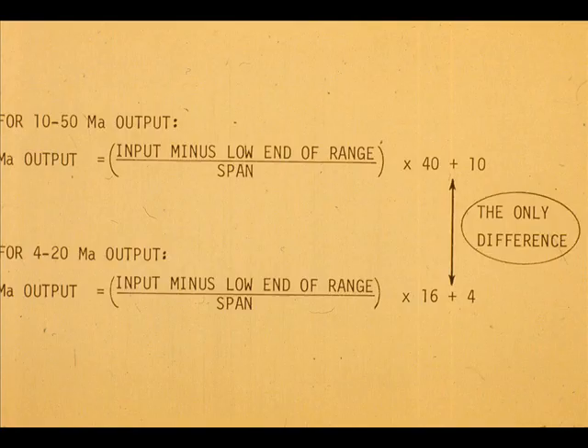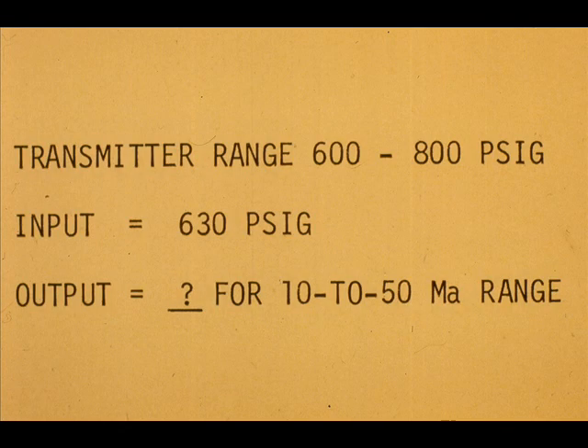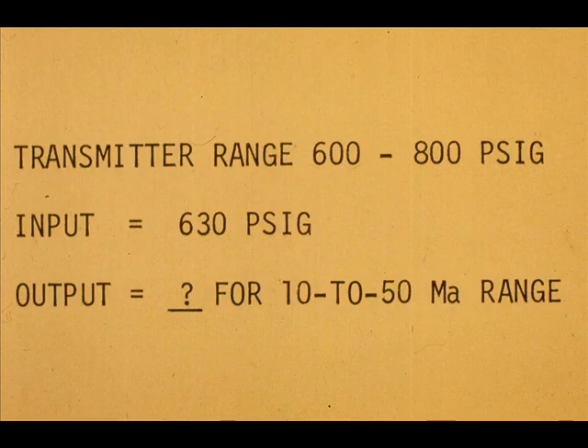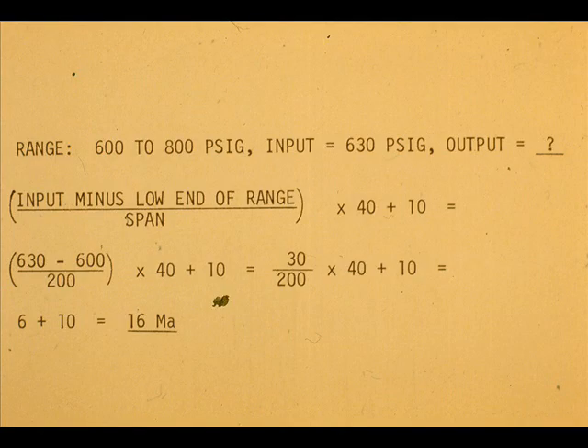The only difference in the two formulas is the output span and starting current. For an example, we shall calculate the milliamp output for a 600 to 800 PSIG range transmitter having a 630 PSIG input. The answer is 16 milliamps.